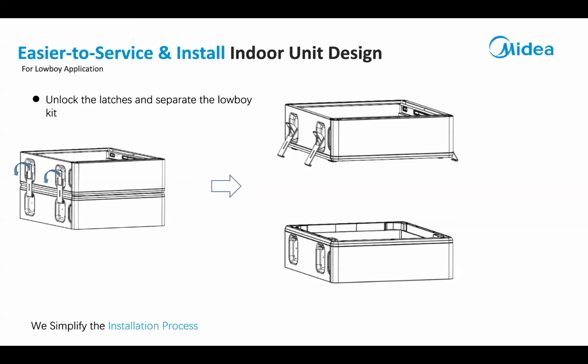In order to separate these modules and install them as a low boy, if you don't use the low boy kit, you literally have to pull the coil and the blower out to be able to screw these to your transfer box. If you use the low boy kit, you secure the low boy kit to the transfer box and you just buckle the modules in place. We do have the kits on order, but they're not here yet. They were just barely getting finished in the development process. So we will have them as soon as we can get them.